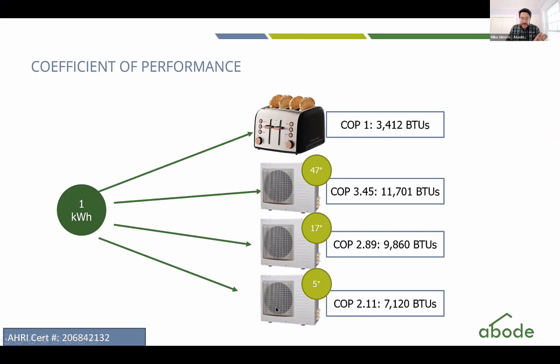This performance is reflective of one specific model number. Do know there are thousands of different heat pumps on the market, and all of them perform differently. But with a well-performing cold climate air source heat pump, typically it's always going to have a coefficient of performance greater than 2 — so always 1 unit of electricity and over 2 units of heat out.